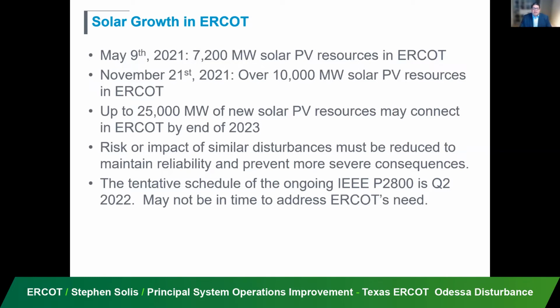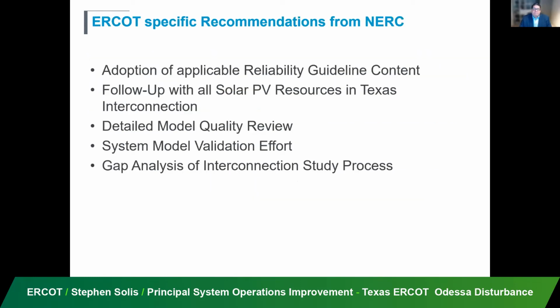Obviously, as you expand your footprint of solar PV resources, if you don't do anything, you're going to have really large losses of megawatts, potentially leading to severe frequency disturbances. And when we look at the new standard IEEE P2800, it has a schedule coming into effect in the second quarter of 2022, and that may not be fast enough. So we're drafting rules as we speak within our region. We're creating an inverter-based resource working group or task force to look at this within our region to really try to adopt and implement as many of these guidelines and rules that NERC has given us to follow up on.